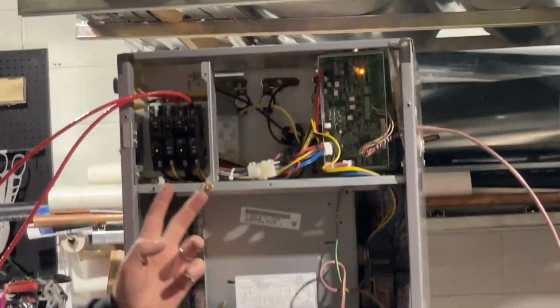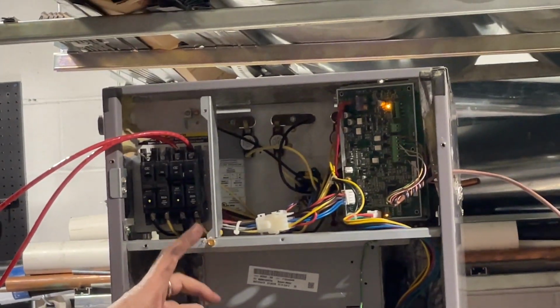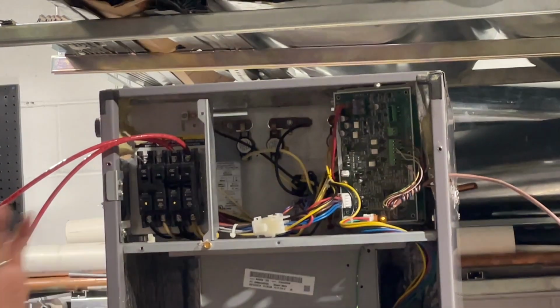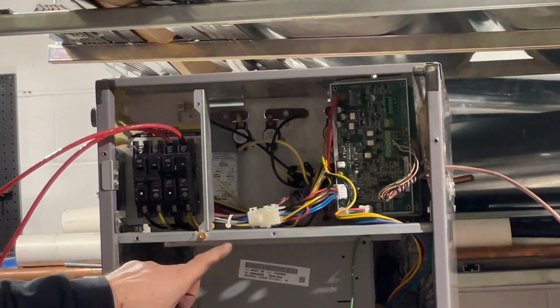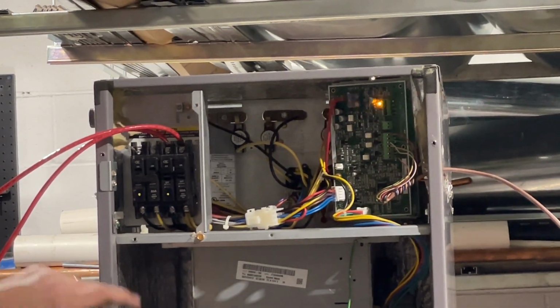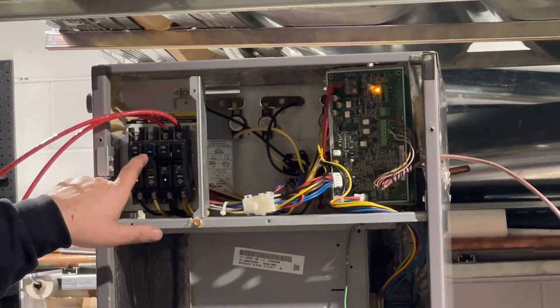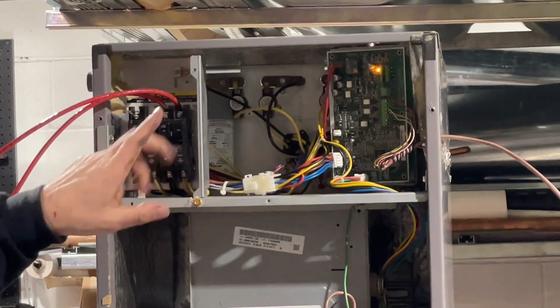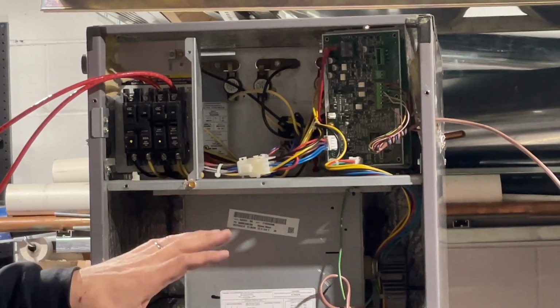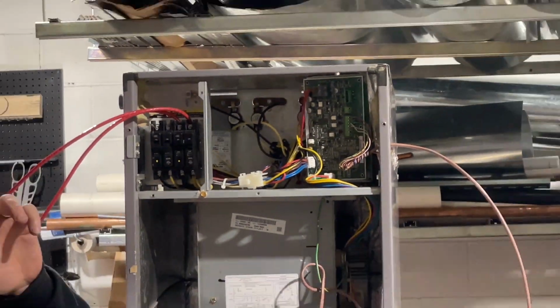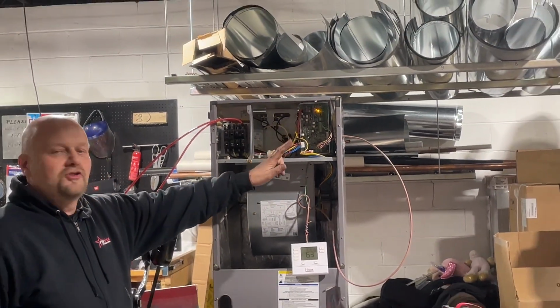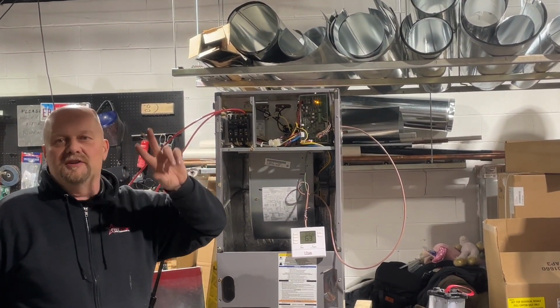two of these sequencers. That's because one of them is for the W1, which is your main heat, and the second one is like a W2, and we don't have that connected because that would be its own separate circuit breaker for the second heat or the auxiliary heat. Most of the time, sometimes you're going to see even three on your control board. You're going to see S1, S2, S3.